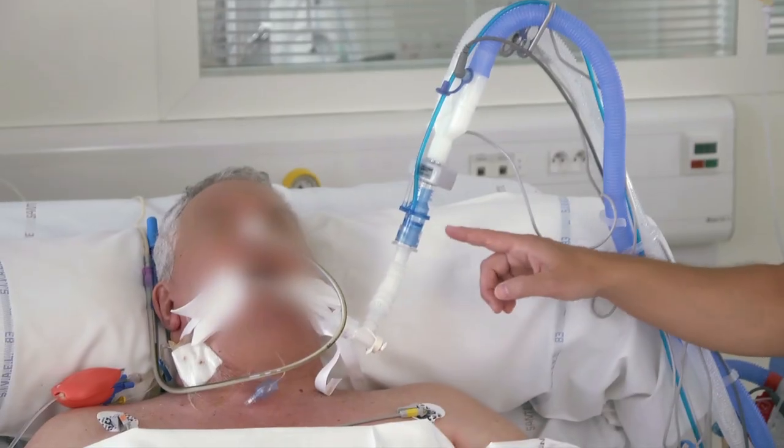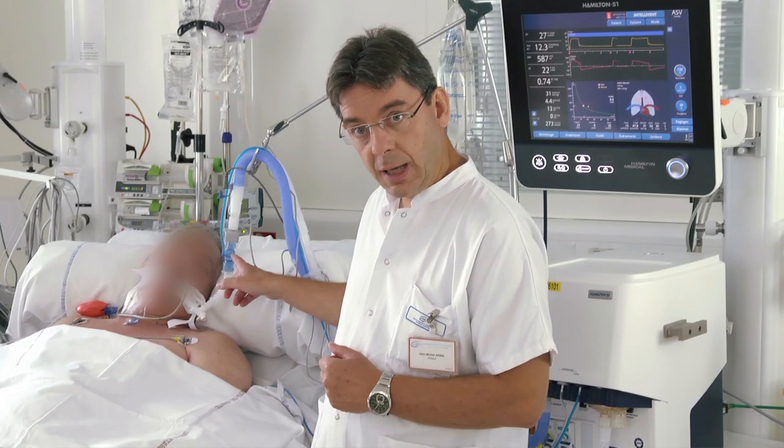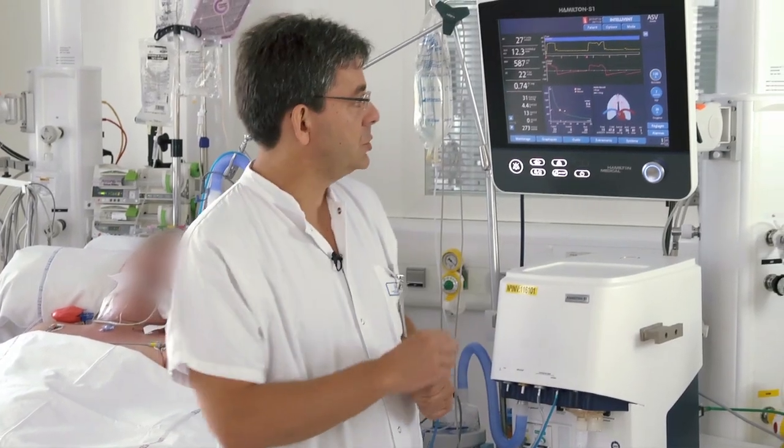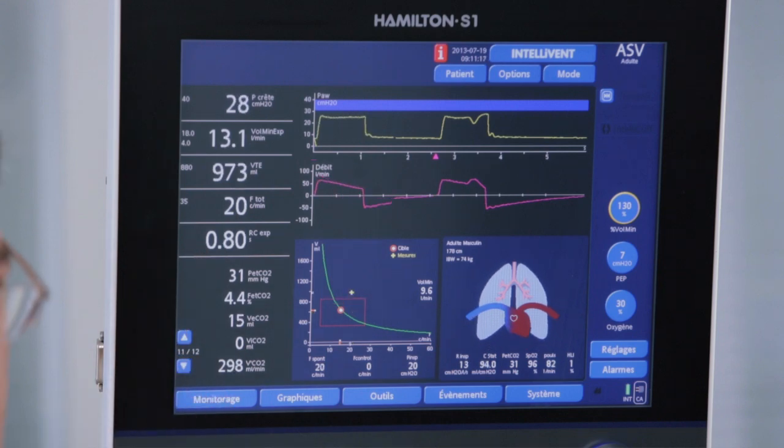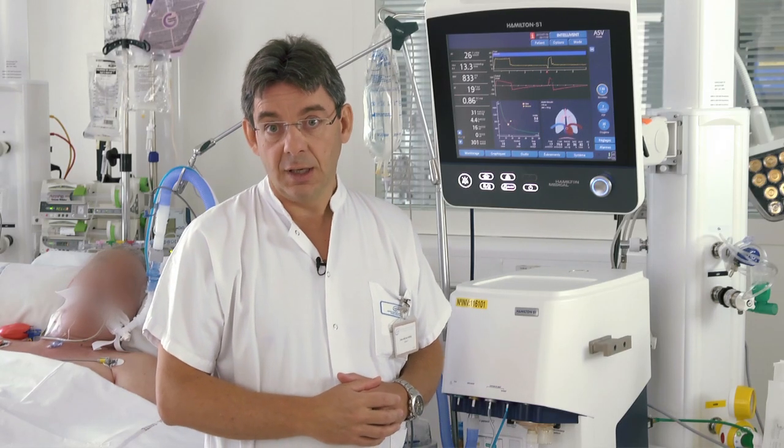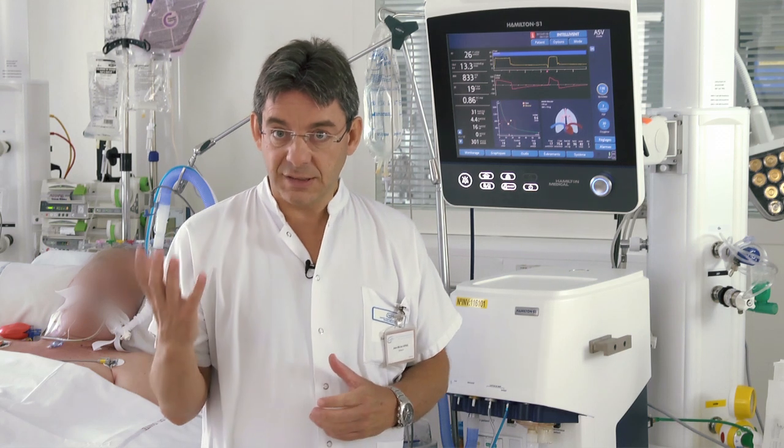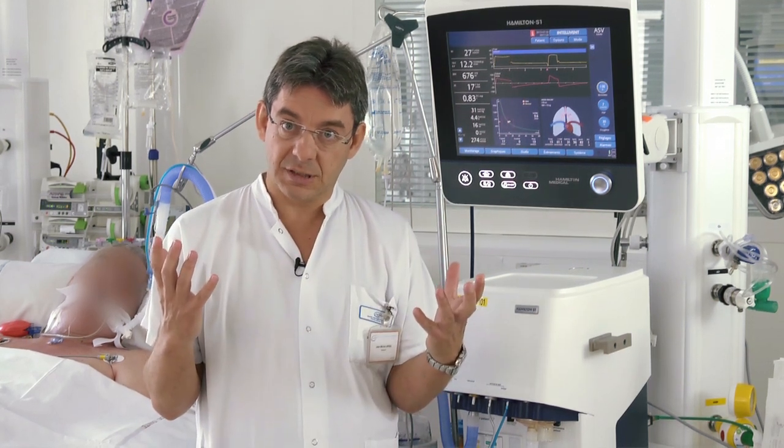ASV is a closed loop mode of ventilation in which the user sets the target minute volume and the ventilator will determine the combination of tidal volume and respiratory rate according to the respiratory mechanics. The ventilator measures the respiratory mechanics using a proximal flow sensor, and namely it measures the expiratory time constant. The expiratory time constant is a mix of the static compliance and the respiratory resistances.